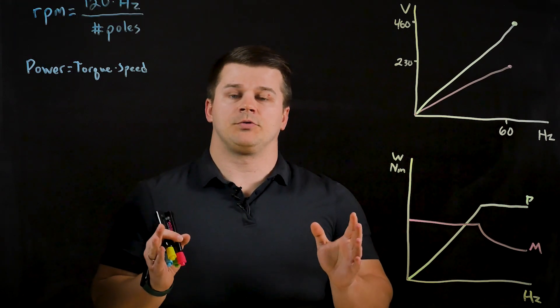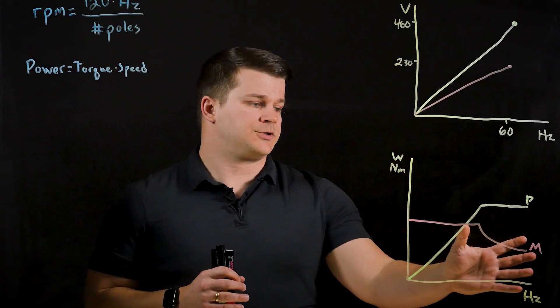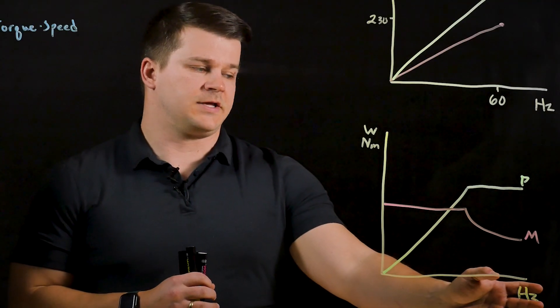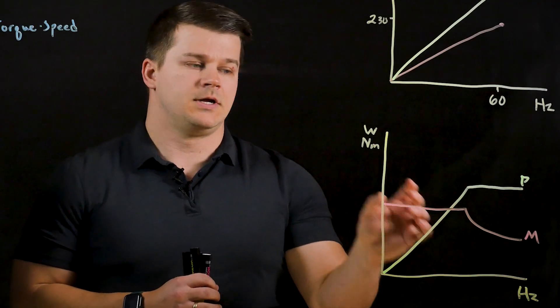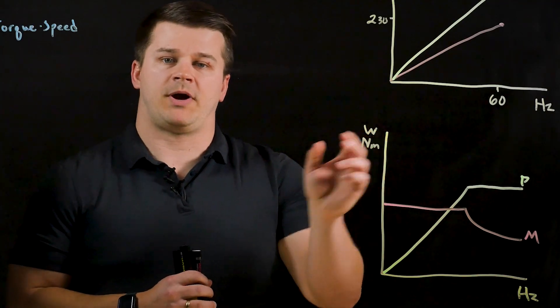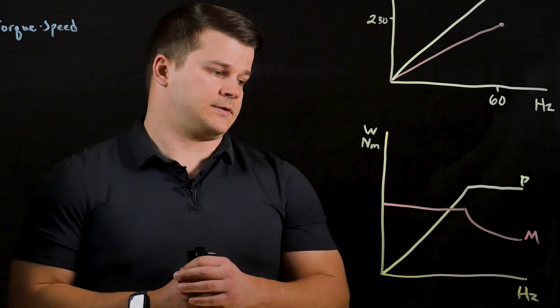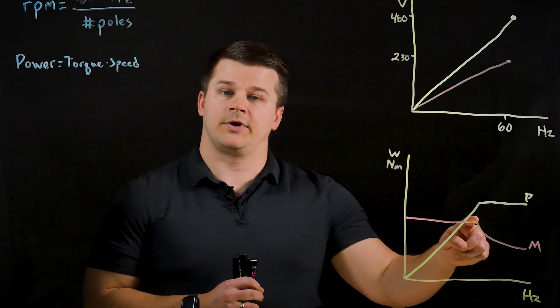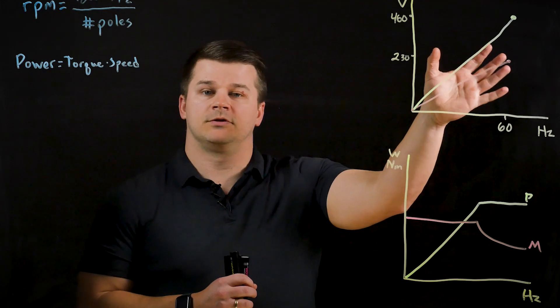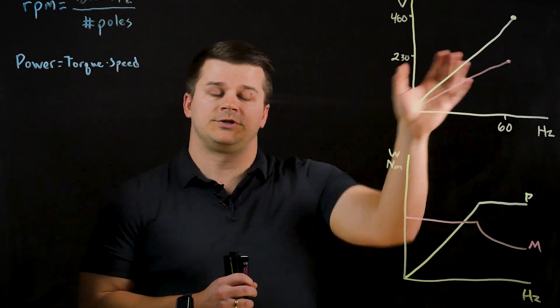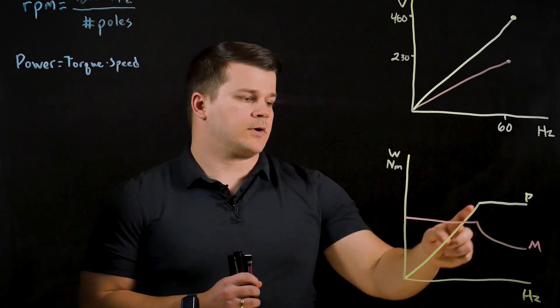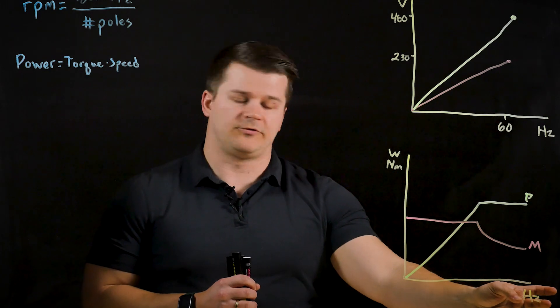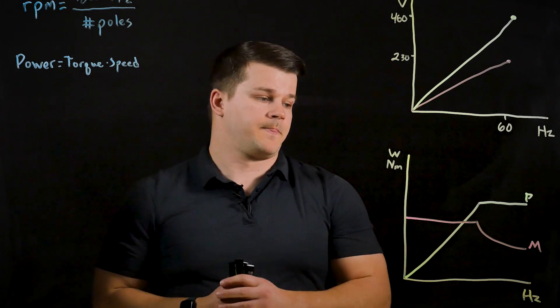All of this information is pulled together and shown on the power and torque curves. Again we have the frequency on the x-axis and this time we have power and torque on the y-axis. The torque is constant until the rated frequency because we're keeping the volts and Hertz ratio constant, and the power is increasing directly with the speed based on this equation.